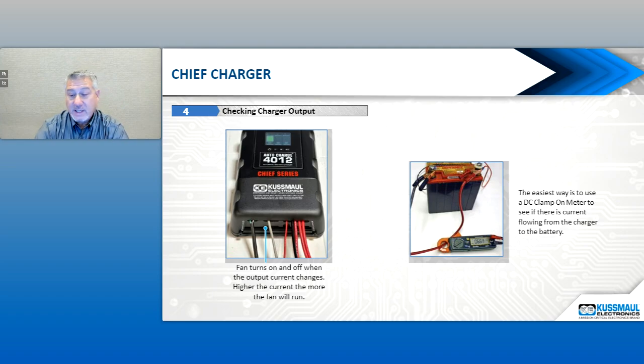The fans on the Chief charger, instead of running at 100%, are variable — the higher the current, the faster the fans run. So if you hear the fans running, you know the charger is flowing current. Just like with the other chargers, the easiest way to check is to take a DC clamp meter and put it around the power cable, and it will tell you what current the charger is flowing.